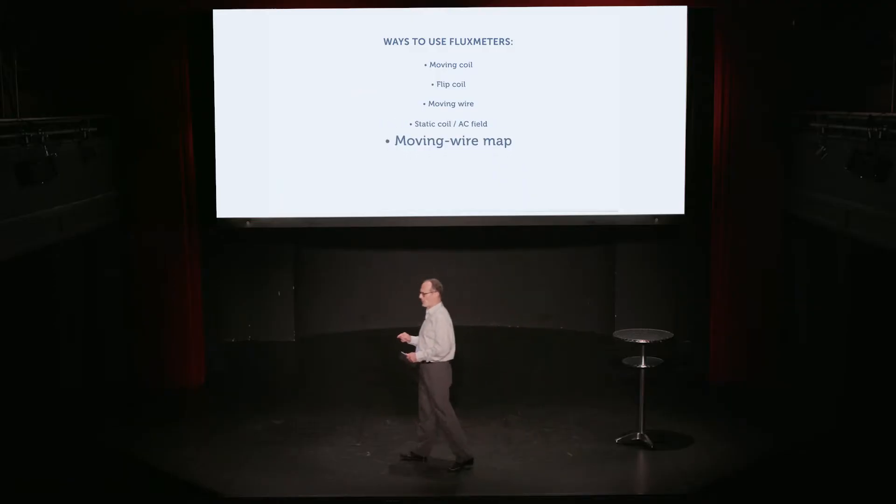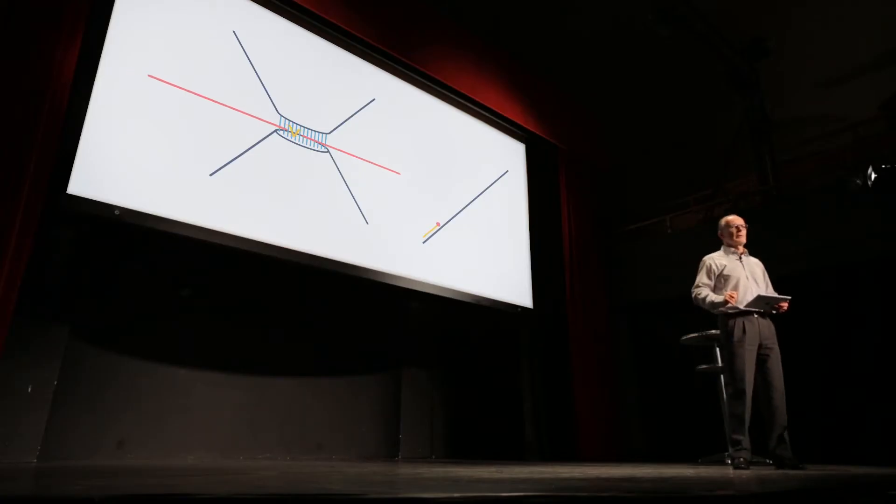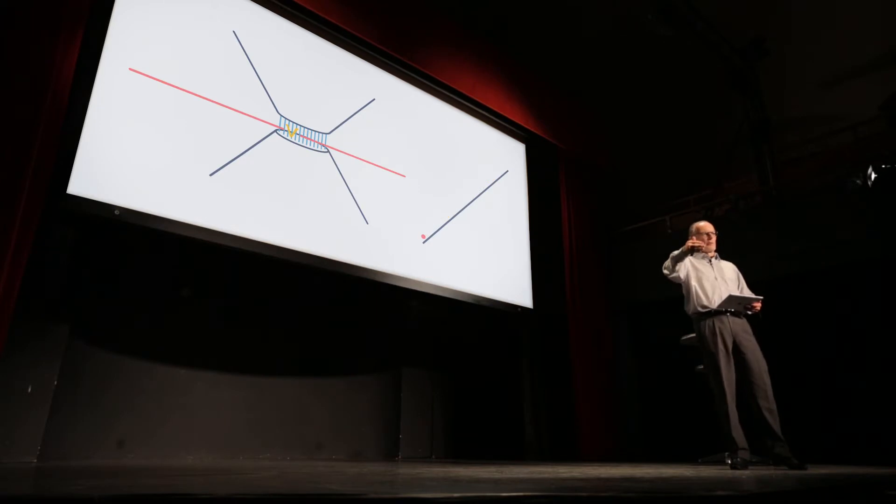One very important feature of flux meters is that you can get a field map practically for free. For example, what I've shown here is a moving wire. And as we move the wire, we are interested not just in the final result when we've gone all the way through the magnet. We're going to save the partial integrals as we move the wire through the magnet. And what we get then is a profile of the field as we move that wire through the gap.